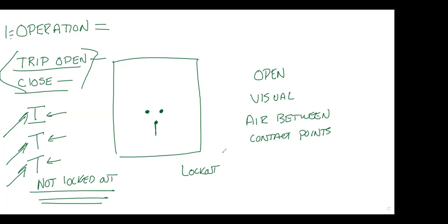Okay, this is not lockout tag out. This is what the reclosing relay is doing. It will go into lockout. When I say human intervention, it might be human intervention via SCADA or on site, but some kind of repair or patrol needs to be done before that breaker can be closed again. Okay. Glad we went over these.